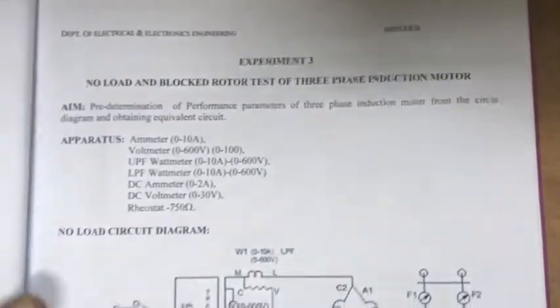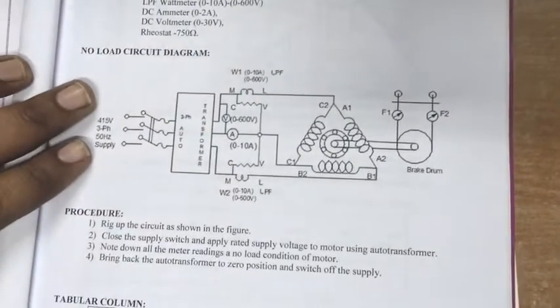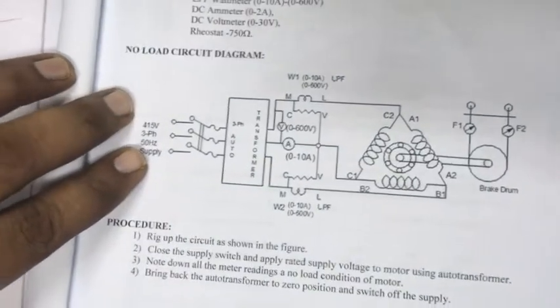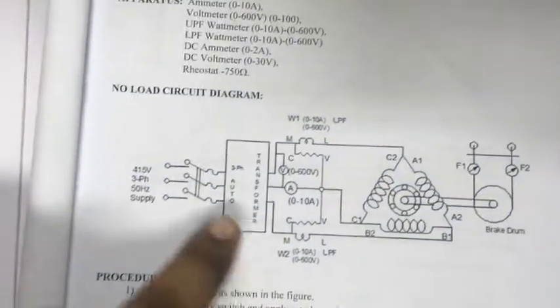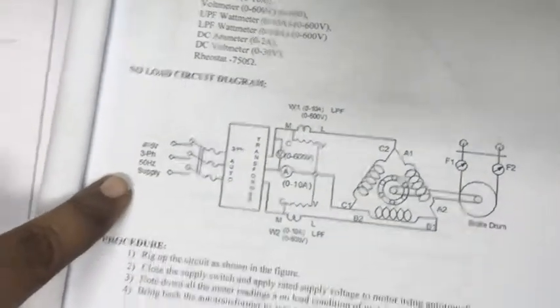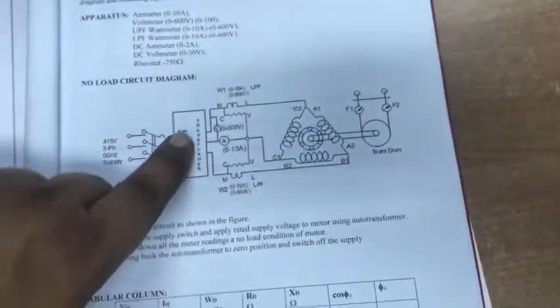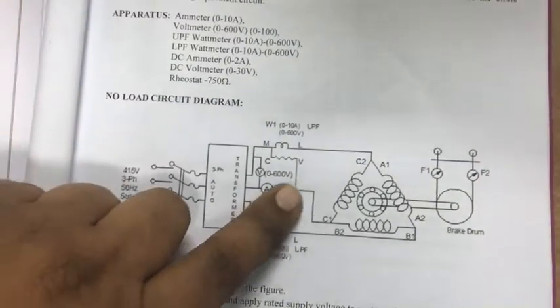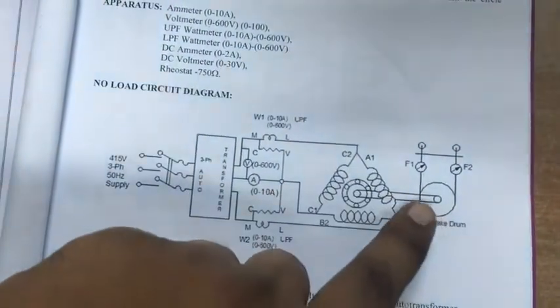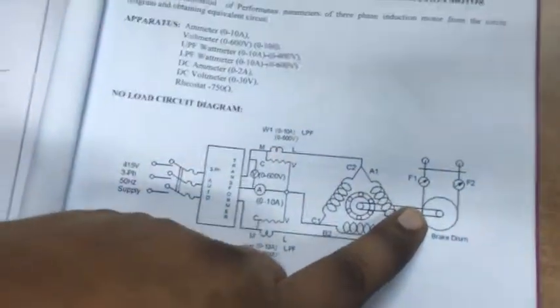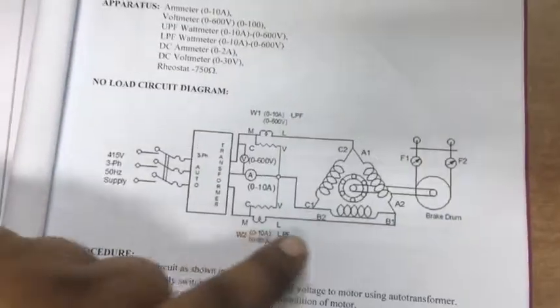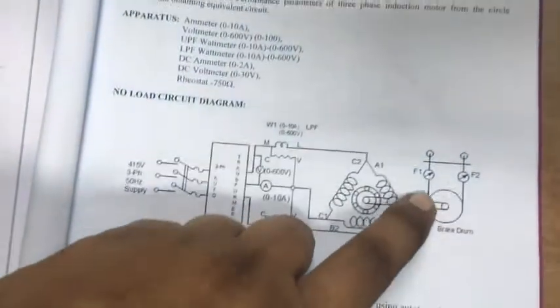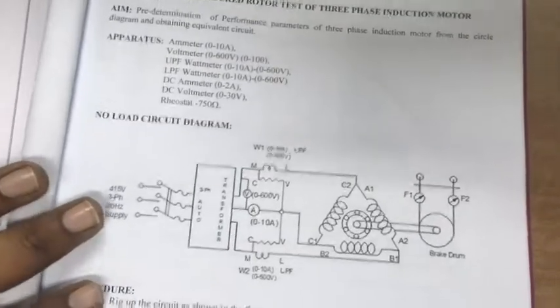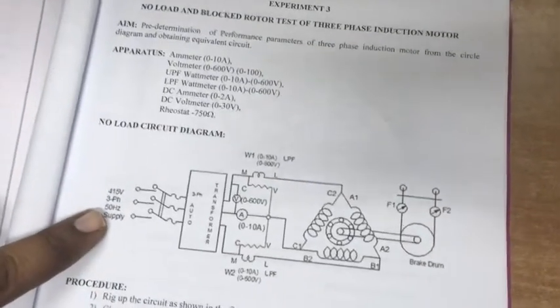So that's it. Now let us go for the no load circuit. While coming to the no load circuit, we are connecting an auto transformer to a three-phase supply, and from the auto transformer we are connecting to the panel boards. Here the motor must be under no load condition, so we have to carefully see that while conducting the no load test the drum must be freely rotatable. So this is your circuit diagram.